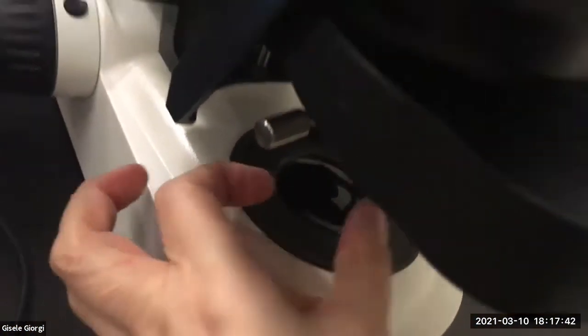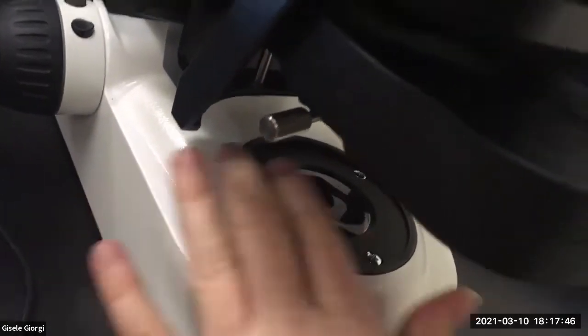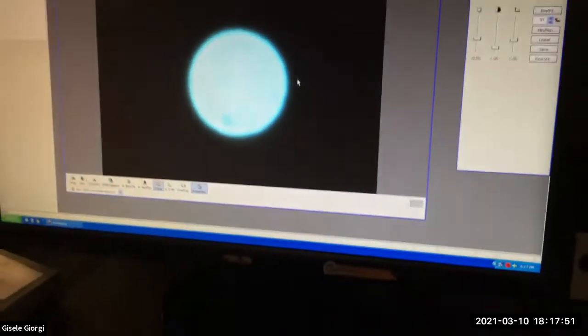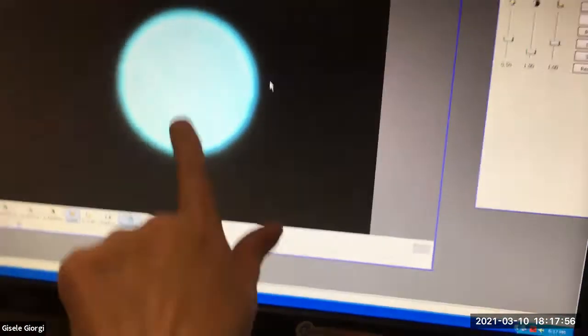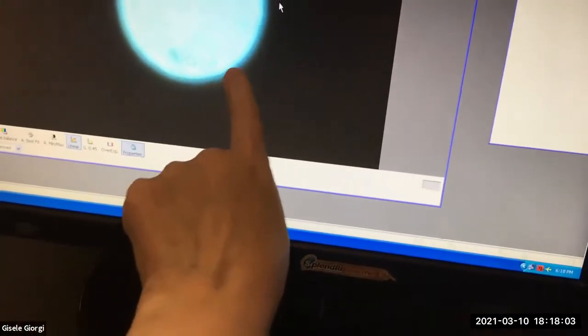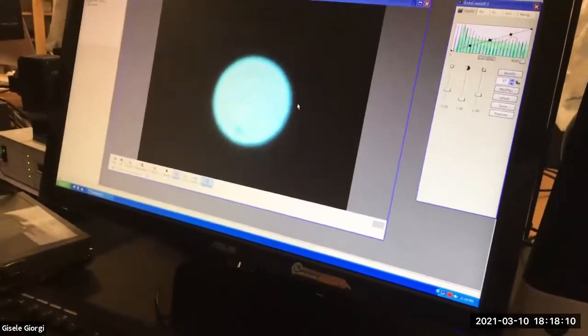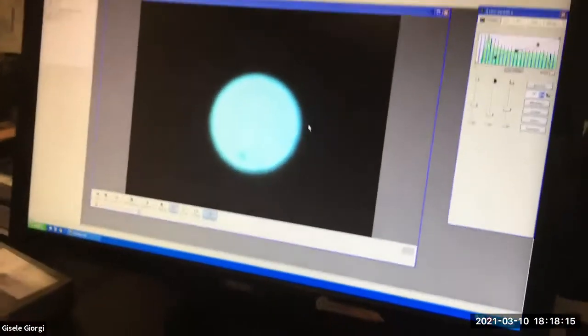So I've basically shut down the field stop in front of the column of light coming out of here. And the condenser is out of focus because first of all, I can't illuminate the whole field, but also you'll notice that when I shut it down and I'm looking just at the edges of this diaphragm, they're blurry. That's no good. We don't like blurry things in microscopy. We always want everything to be in focus.